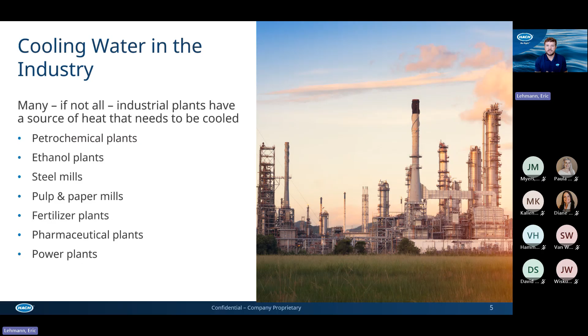There are really three main means of cooling that water down, and I'm sure you're familiar with these. You might have a once-through type system, where steam from the plant comes into the condenser and back to the power plant and boiler system. The way that works is it uses water from a lake or river, brings that cold water in, cools the steam down without really coming into contact with the condensate, transfers that heat to the cooler water, and then discharges it back. That's considered more of a once-through type system.